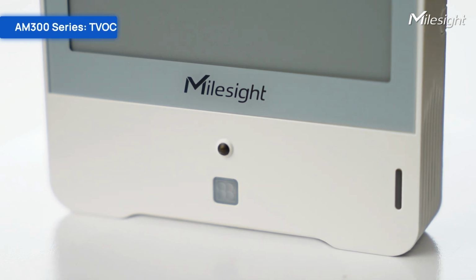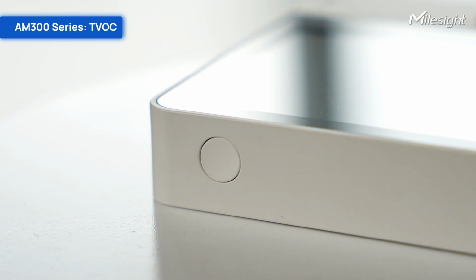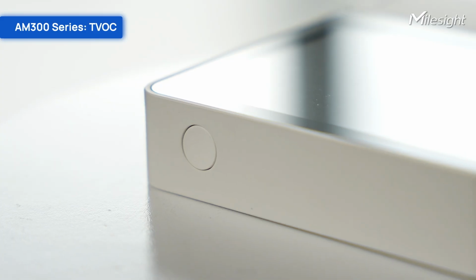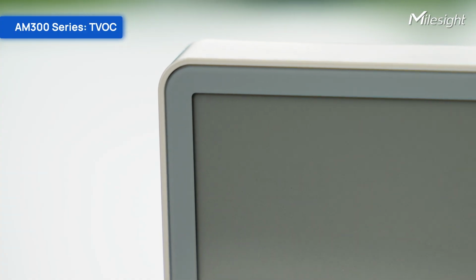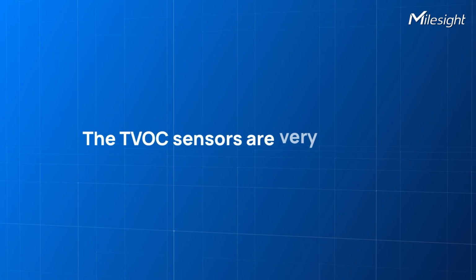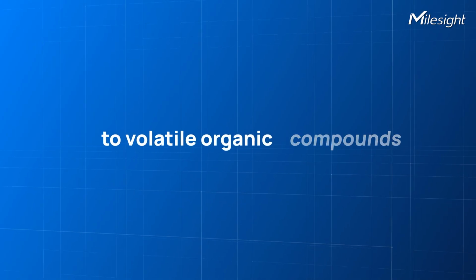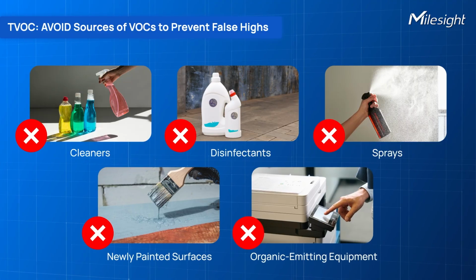In addition to the points mentioned above, if your device is an AM300 series model, be sure to avoid the following factors that may affect TVOC readings. The TVOC sensors are very sensitive to volatile organic compounds. Please keep away from cleaners, disinfectants, sprays, newly painted surfaces, or organic emitting equipment such as printers/copiers, to avoid falsely high readings.